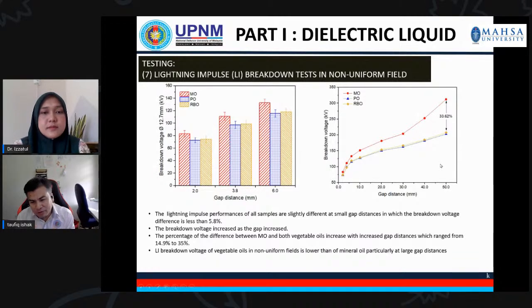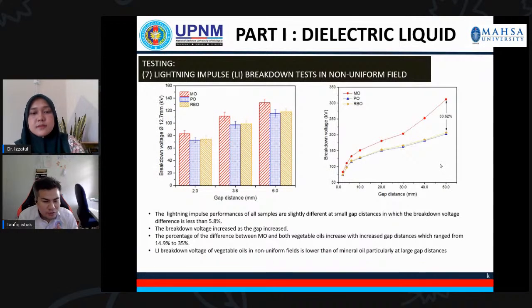So why do we need to study a small gap and a larger gap? Inside the transformer, different gap distances appear. In some places you get a very small gap distance. Some parts between the tank and the winding can have a larger gap distance, maybe around 15 mm or larger. That's why we need to study both smaller and larger gap distances, to cover all the areas inside the transformer. However, even though the gap is quite big at the larger gap distance, it's still reasonable. It does not go beyond 33%, and this result is in line with other results for different kinds of vegetable oil.